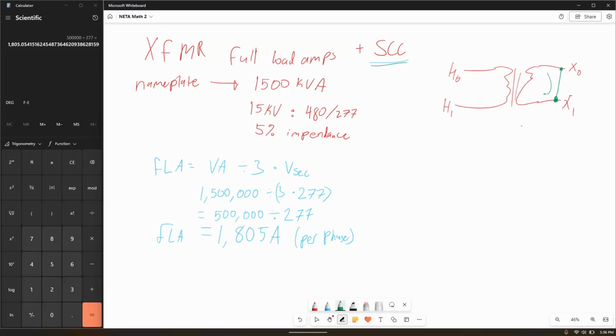And what is the magnitude of that short circuit current? Well, we've got another formula for that, which is short circuit current equals VA, the rated VA rating of the transformer from the nameplate, divided by our secondary voltage, VSEC. And again, this is phase to neutral, right? It's our line to neutral. That's our 277 VSEC multiplied by our percent impedance.